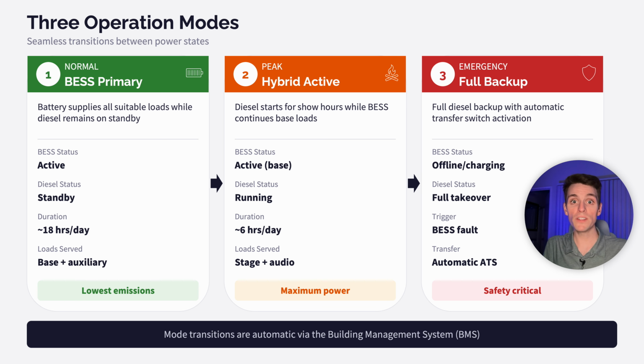The system operates in 3 modes. During normal operation, about 18 hours a day, BESS handles all suitable loads while diesel stays on standby, achieving the lowest emissions. During peak show hours, roughly 6 hours a day, diesel automatically starts for audio and stage loads while the BESS system continues to cover base loads. In an emergency, automatic transfer switches move everything to diesel until the BESS system can recover. Transitions are managed automatically by the building management system.